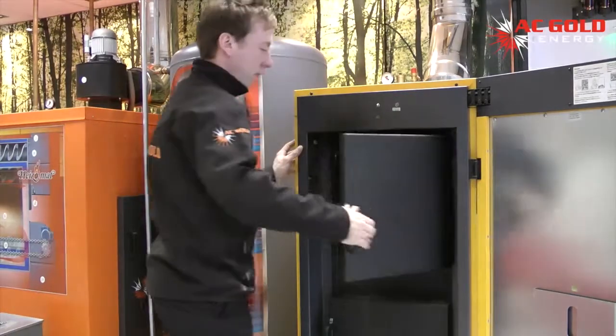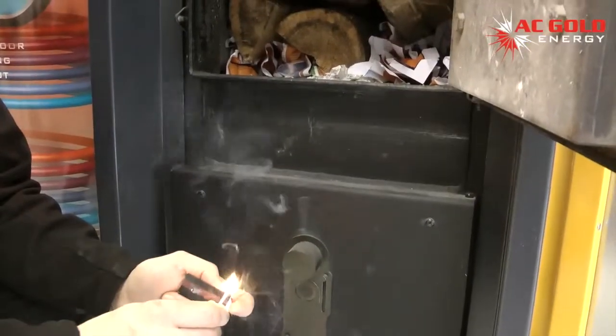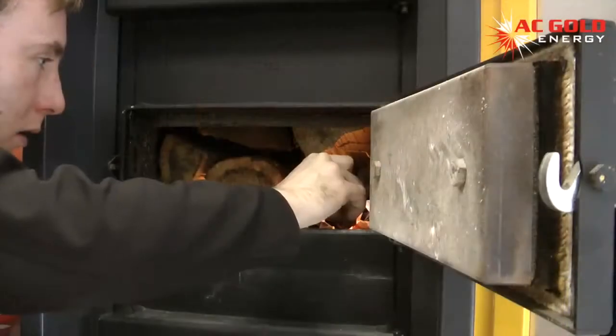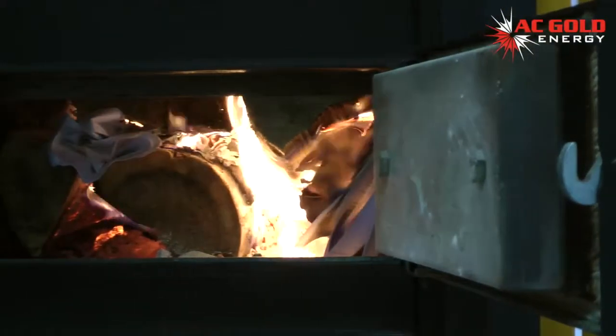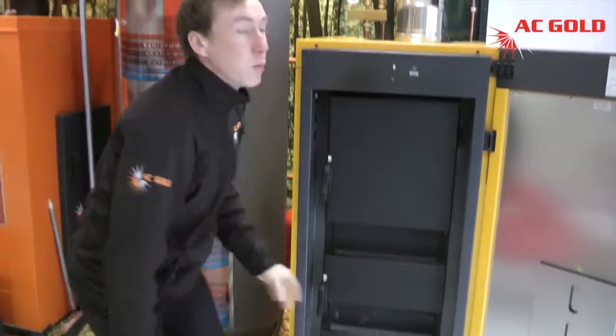Lighting the boiler is also very simple. The induced draft flame ensures rapid ignition. Once a required temperature of 100 degrees on the flue gas has been reached, you can then close the igniting door and walk away.